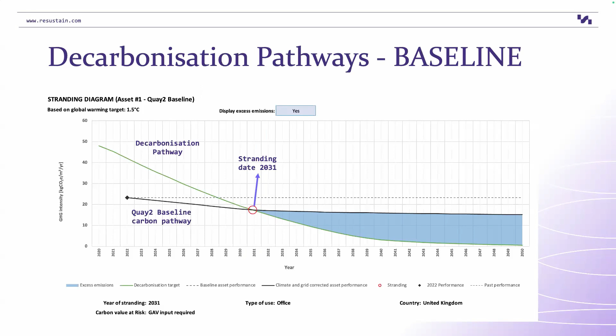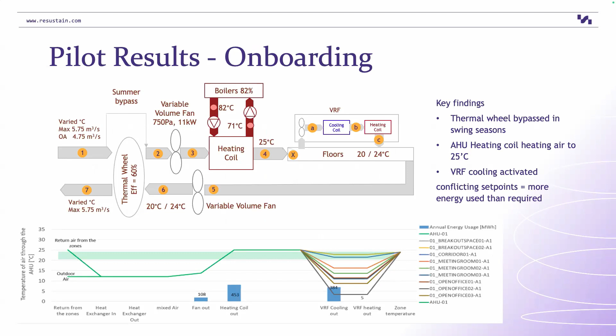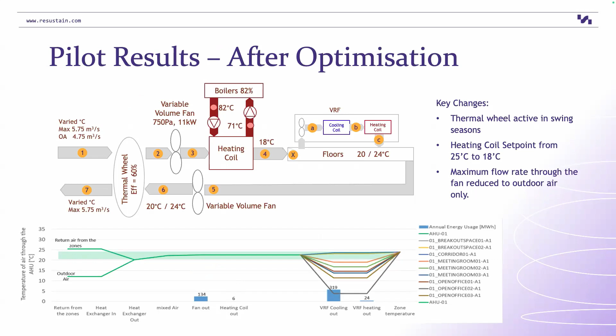The stranding date here when we got there was 2031. Again, we did the analysis through the HVAC system, and what we noticed was that the thermal wheel was being bypassed in the swing seasons when it shouldn't have been, and the air handling unit was providing 25 degree supply air temperature, which was activating the cooling on the VRFs.